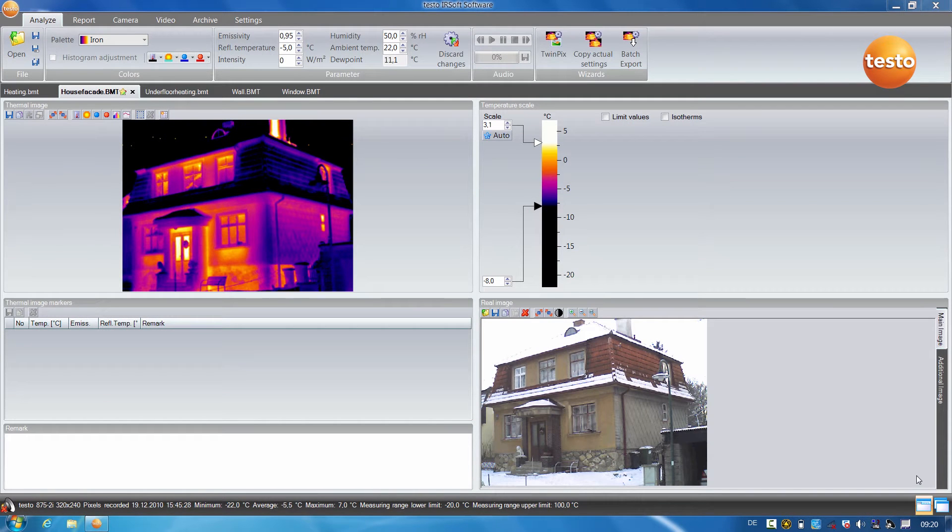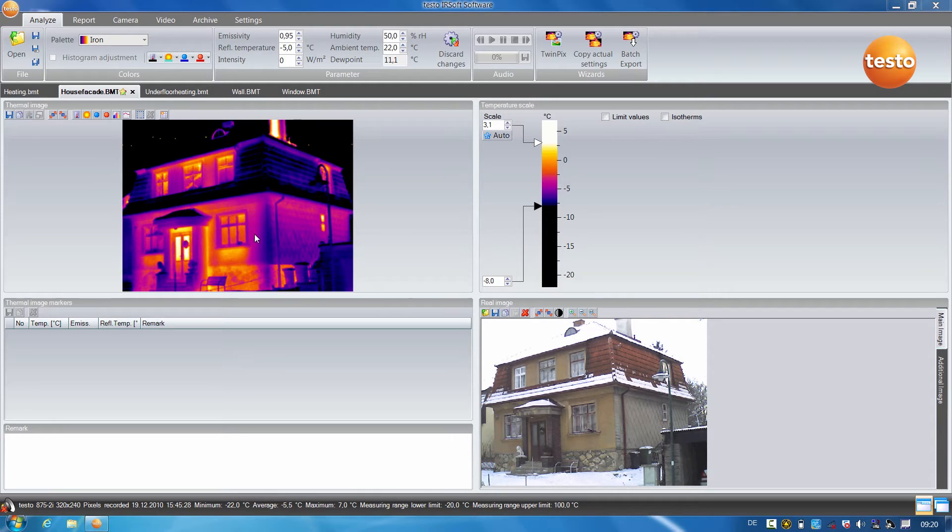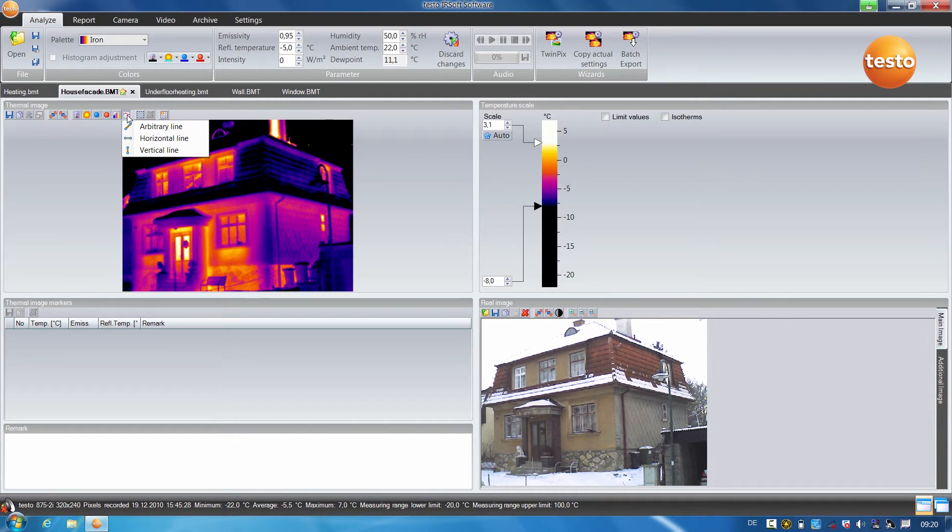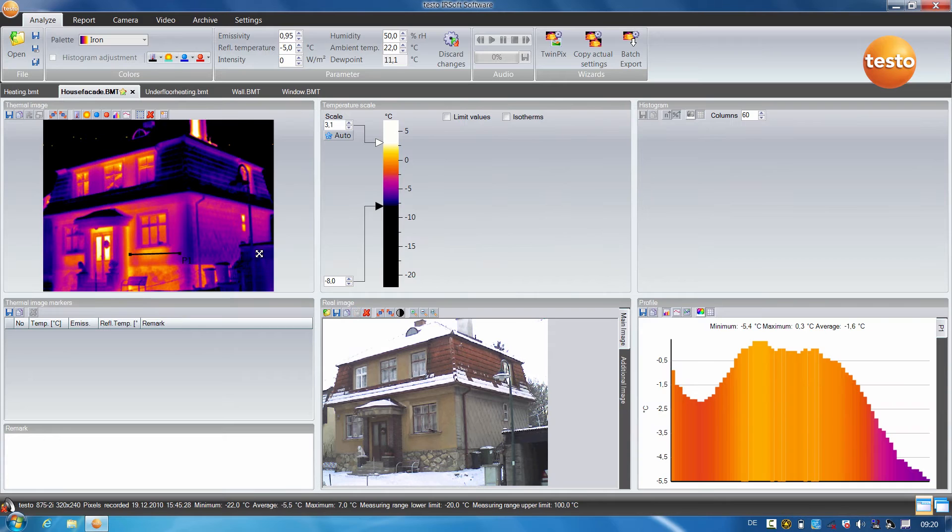In this thermal image, there are cold bridges visible on the front of the building, here under the windows. Using the Profile Line, you can quickly and easily show the customer the temperature difference to the rest of the building front. To do this, simply select the Profile Line function, mark the desired area, and we can already see the temperature curve of the profile line in the diagram below.